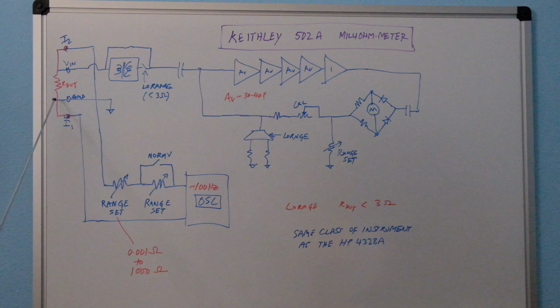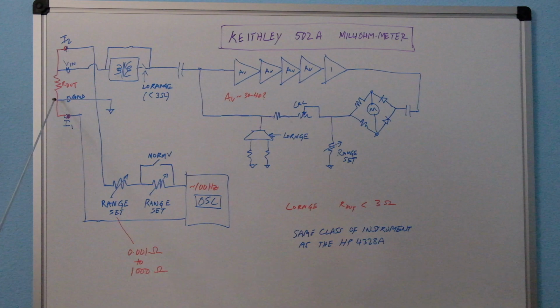To describe this again, there are 11 ranges over here, and depending on whether you're operating in the normal mode or the low voltage mode, you can switch using the main switch. And there are 11 ranges here, switchable again with a rotary switch. Basically there are 4 terminals, a Kelvin connection, and there are 4 leads actually, which are not joined together.